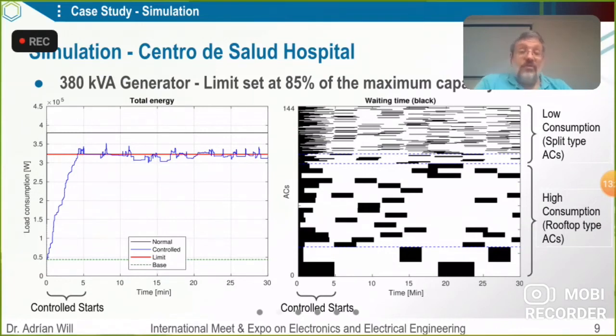For security reasons, and according to the manufacturer, you need to set your limit at 85% of the maximum nominal power. If you go above 90%, your energy starts to flicker and your main phase gets overwhelmed, and you can have an outage if you go over 90 to 95%. Experience also shows that if you do it, you will really get an outage, and the generator will go offline.